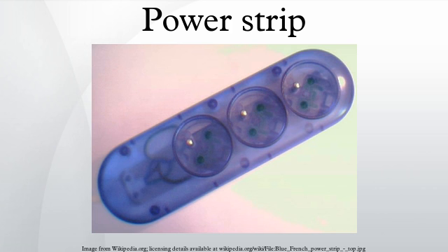U.S. regulations. Underwriters Laboratories Standard 1363 contains requirements for relocatable power taps. Included in the scope section of the standard is the statement: "1.1 These requirements cover cord-connected, relocatable power taps rated 250 VAC or less and 20 A AC or less. A relocatable power tap is intended only for indoor use as a temporary extension of a grounding alternating current branch circuit for general use." The National Electrical Code recognizes the power strip as a multi-outlet assembly in Article 380.